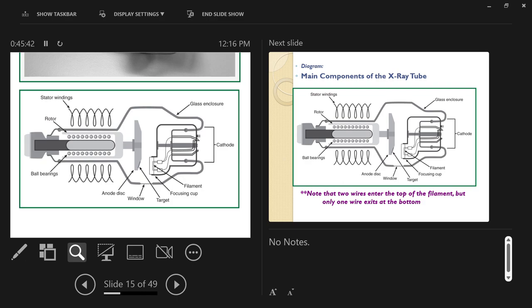The anode disc spins and serves as the positively charged surface for electrons to run into. The cathode side has two filament wires to choose from and creates the space charge — the cloud of electrons. Electrons travel from cathode to anode, hitting the anode and creating photons. The glass is slightly thinner at one spot — a window — because anything in the path of the x-ray beam will partially absorb it.